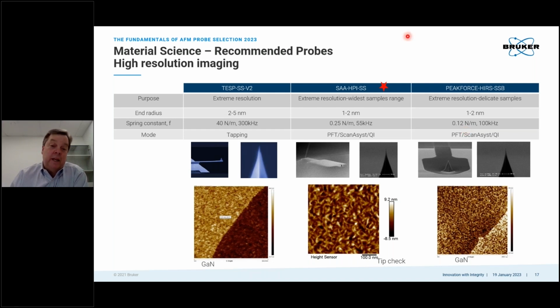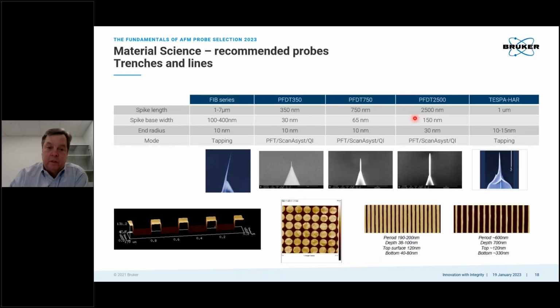And I like this probe a lot. Actually, this is the SAA, which is ScanAsyst-Air-HPI-SS. So it's a 1 nanometer probe on that ScanAsyst-Air-HPI structure. It has a low spring constant, 0.25 newtons per meter. So it does a really nice job at real high resolution. And then this other one as well is very similar, a little shorter probe. So these are both good options.